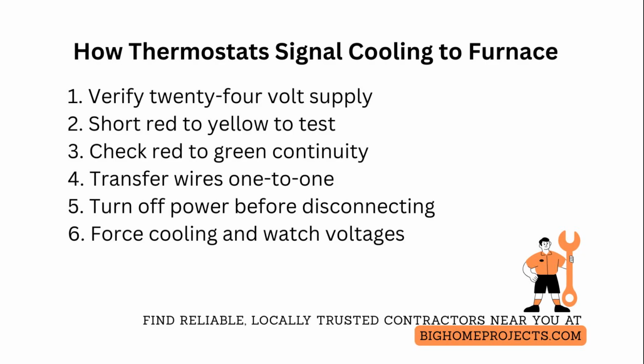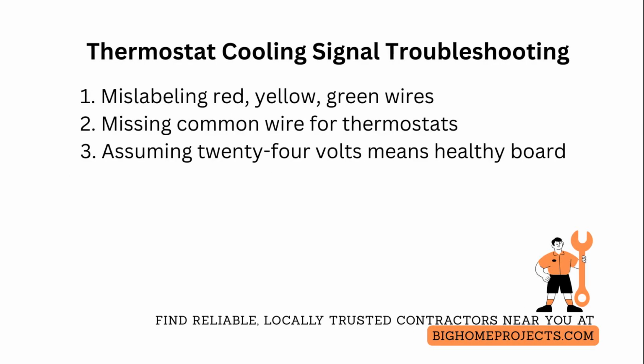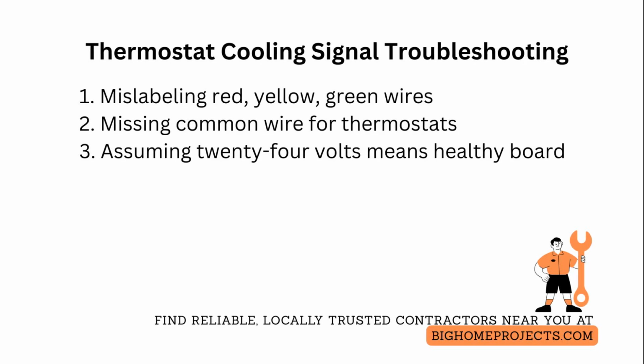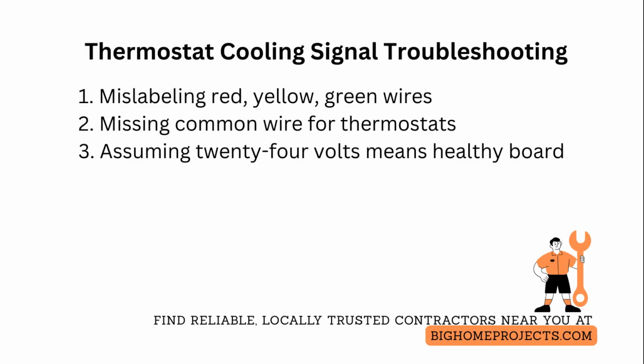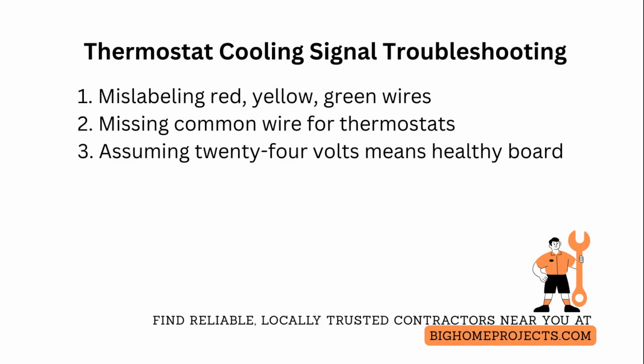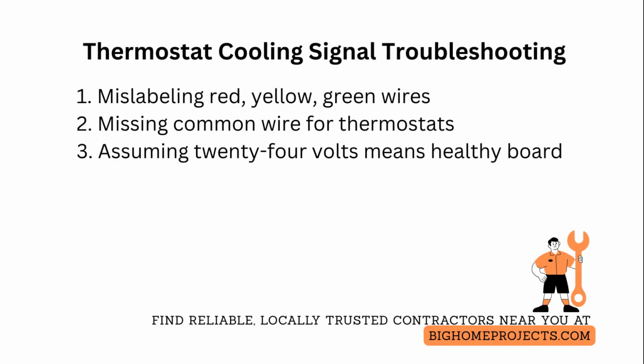One of the most frequent thermostat wiring mistakes is mislabeling or mixing up the red, yellow, and green wires, which leads to no cooling or no fan operation. Fix this by labeling wires at both ends, using a meter to verify continuity, and following the common color to function mapping during installation.